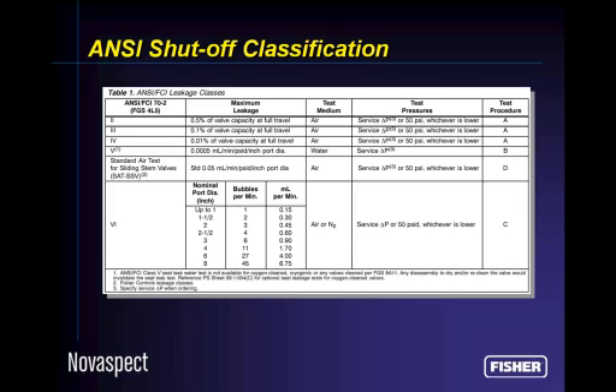One point I want to make about this, and we won't dwell on this a lot as a severe service consideration, but don't over-specify the shutoff requirement for your valve. If you specify a Class 5 or 6 valve when actually a Class 2 would suffice, we make a lot of design differences to that valve. Everything gets bigger, the bonnet gets bigger, the stem gets bigger, the actuator gets bigger to provide bigger thrust to push plugs against seats with more resilience. So everything gets bigger and more costly if you specify a very tight shutoff valve.